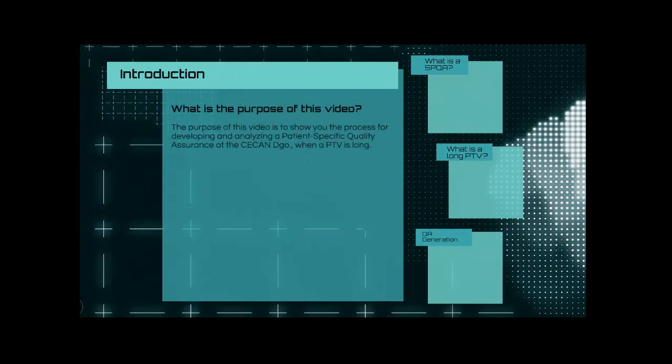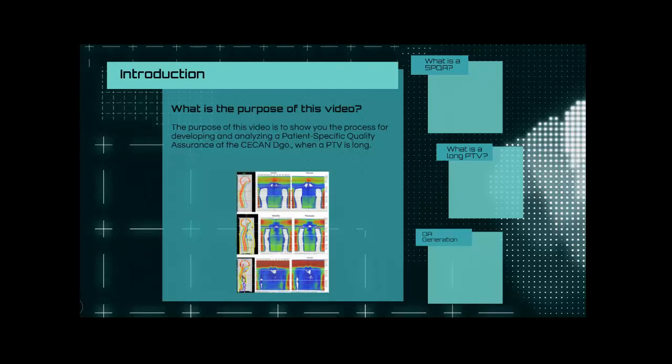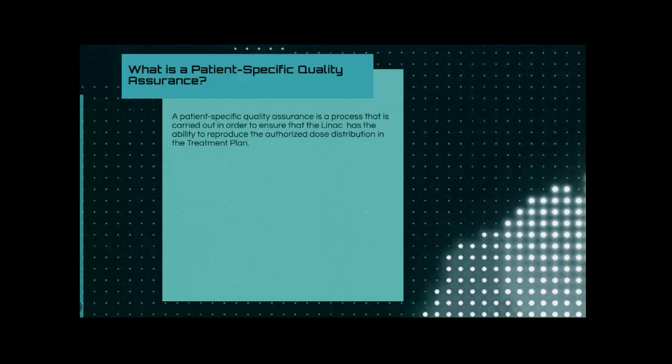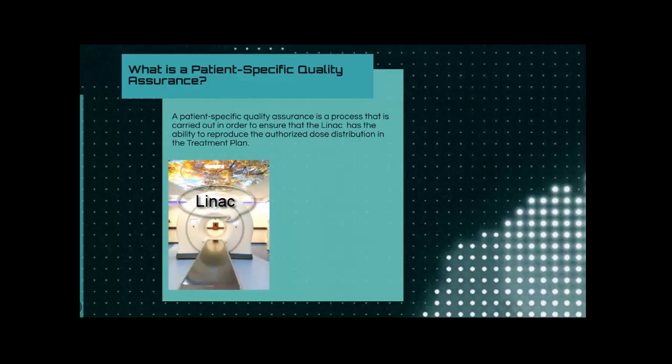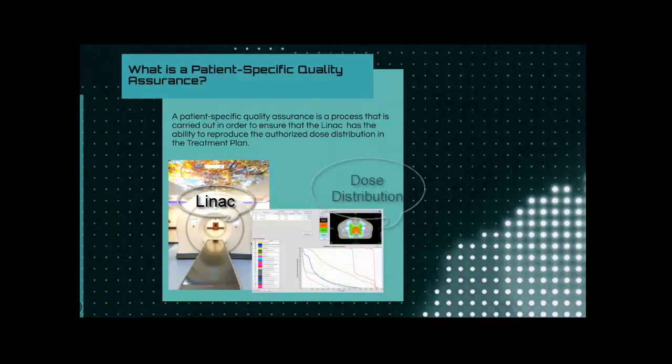Introduction. What is the purpose of this video? The purpose of this video is to show you the process for developing and analyzing a patient-specific quality assurance at the CECAN Durango when a PTV is long. What is a patient-specific quality assurance? From my point of view, it's a process that is carried out in order to ensure the LINAC has the ability to reproduce the authorized dose distribution in the treatment plan.